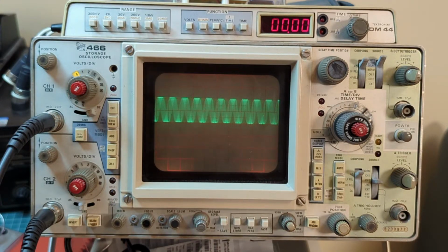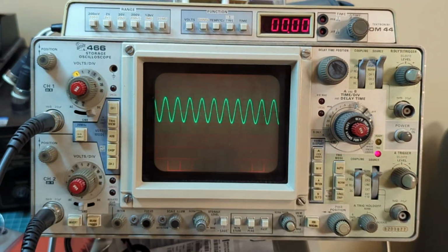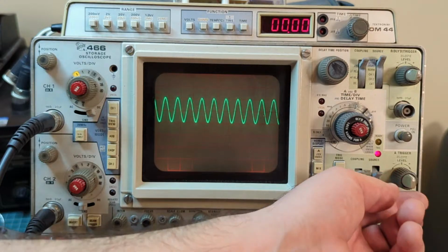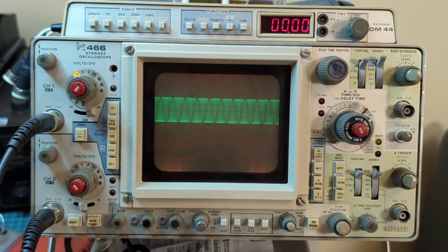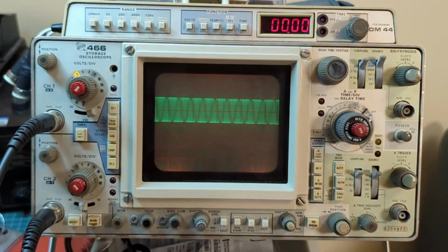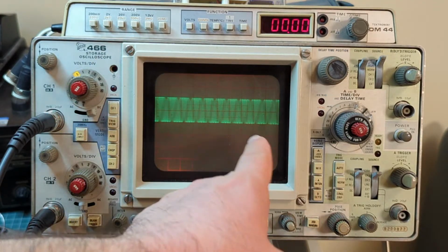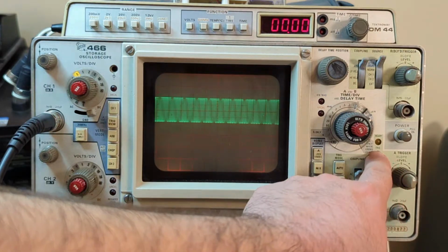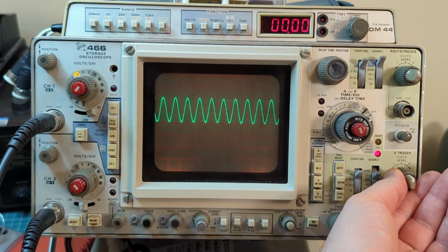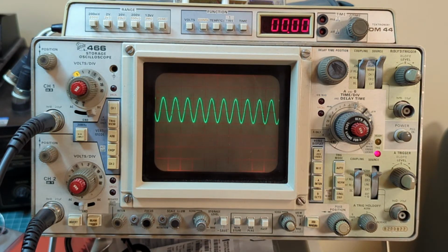So yeah, if only there was a way to do this automatically, right? Well, there is a way to do this, and this is called the trigger circuit of the oscilloscope. What it usually does is that it has some sort of comparator inside, and it compares the input signal against a fixed reference voltage. This is basically what the trigger circuit does, and you can adjust the reference level using this knob, which is the trigger level. So if the trigger level is out of the range of the input signal, then the scope is untriggered, which is indicated by a running trace, and which is also indicated by the trigger light that goes out. So you have to adjust it until you get a stable trace and the trigger light comes on.